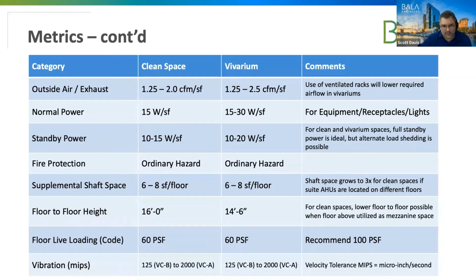And sometimes in projects we've done in the past, we'll run the room at, say, 6 air changes instead of 8 to 15, because the racks themselves, since they're ventilated, are containing the odors, and it maintains a nice air change rate within the rack itself, much higher than 6 air changes, because the volume of those racks is much smaller. So again, something to think about when you're in the programming phase to understand what the client might be utilizing as far as type of housing cages. On normal power, we have a pretty wide range here.